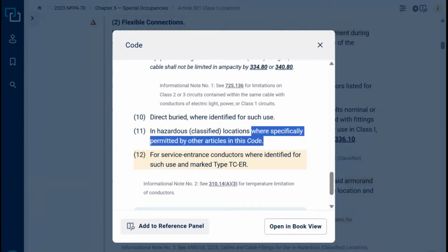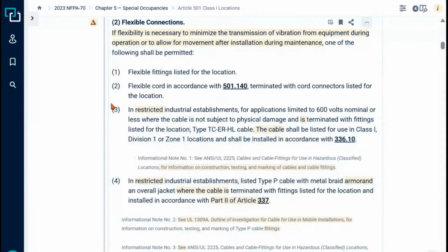But then it ended up directing you back, saying okay, but you still have to meet the requirements for installing the tray cable itself. So you just can't say, ooh, I can use tray cable - you still got to follow the tray cable rules. So that's a good example of how it kicks it back and forth in the code.